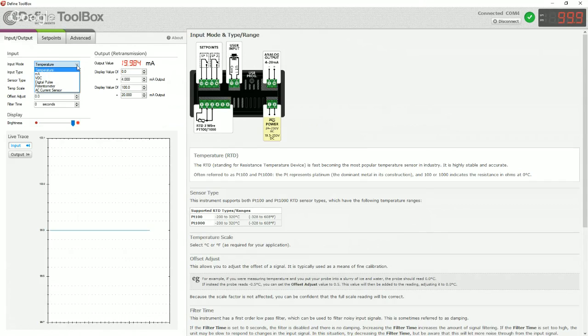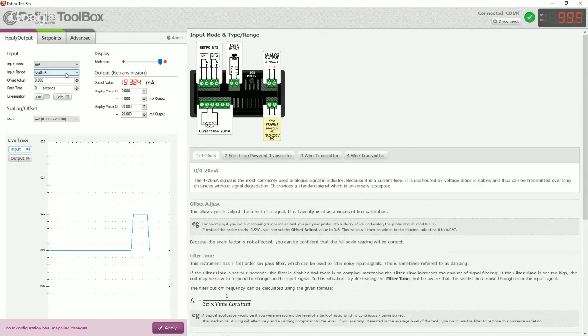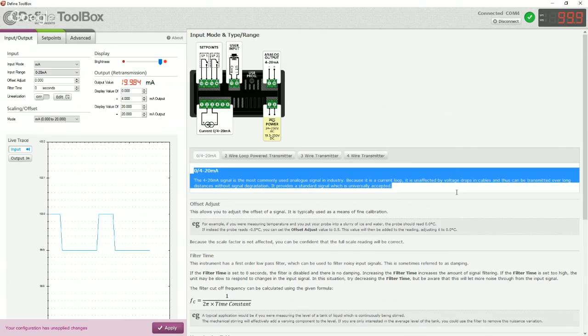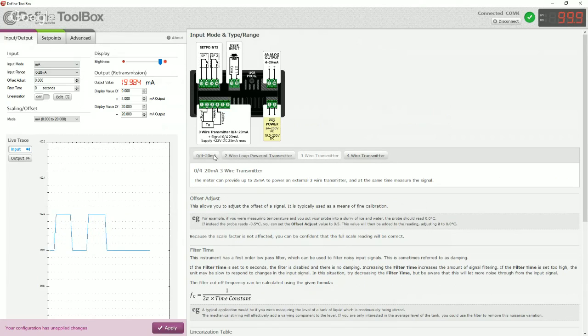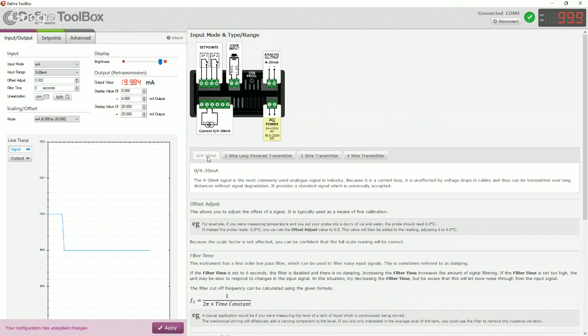We're going to set the input into milliamp mode. So I did that by clicking here on the input mode box, and so you can see we've got a range. So we click milliamps, and then you'll notice that straight away the dynamic help content to the right here has changed, and it now has the 0 to 20 milliamp help text here telling us what the mode does. As I go through and click on more things, this will keep changing, so keep an eye on that. The other thing it does is it shows us here how to use different kinds of transmitters with this milliamp mode, but we're going to use the first option here, which is 4 to 20 milliamps, and that shows us which pins we need to connect into.